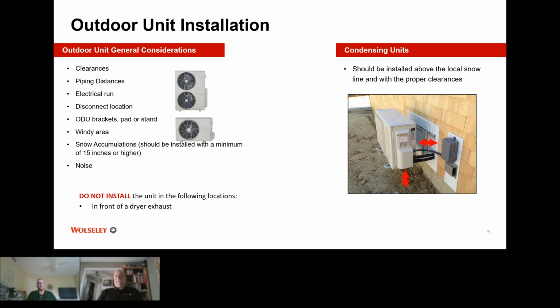Electrical run, basically how far do you want to run your power from your main boards or from your main panel to the units? And do you have room in your panel, first of all, before you buy one? You've got to make sure you have enough room in there to be able to accommodate the units. Disconnection, that's the little box you see in the picture to the right of the mini split, on the right-hand side. And that's there so that when the technician goes to do work on it, he can pull the power there and then he knows the power's off so he doesn't get injured.